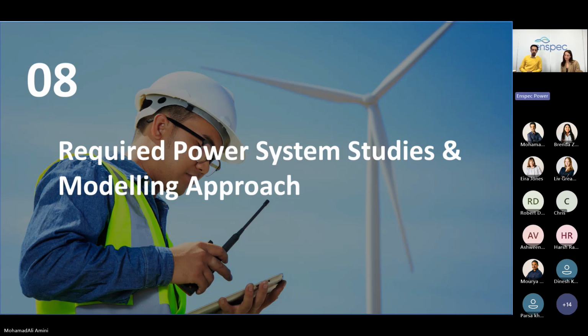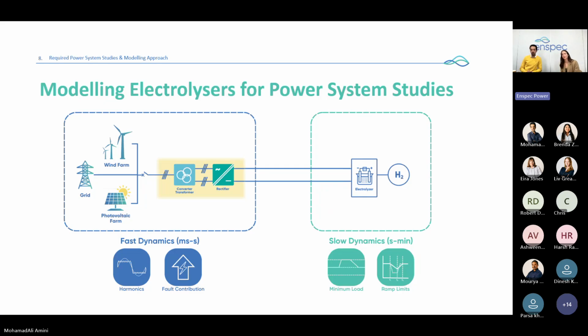In terms of the required power system studies and modeling approach, in order to study a hydrogen electrolyzer plant, the model needs to have two different layers. The first layer is about the electrical components, like the grid model, the transformer, or the rectifier itself. The second layer will encompass the electrolyzer and downstream hydrogen flow rate.